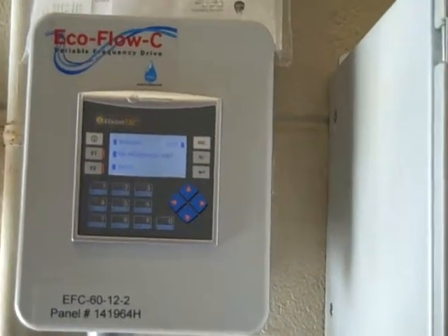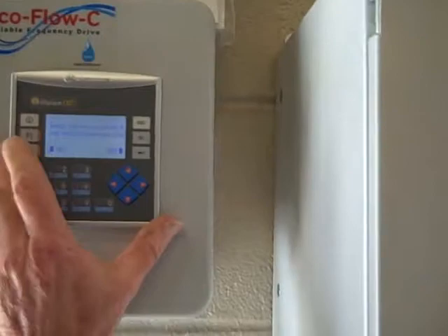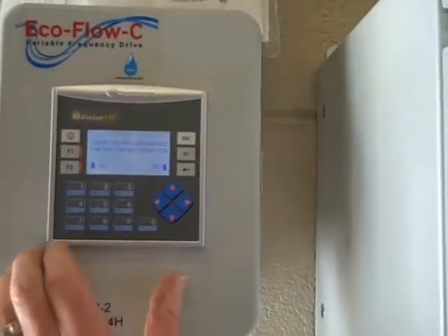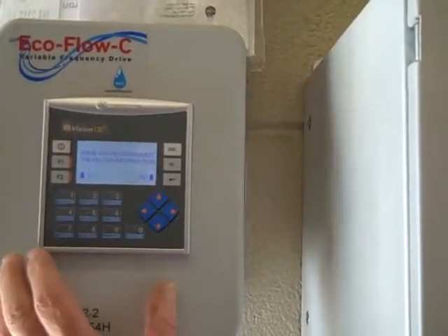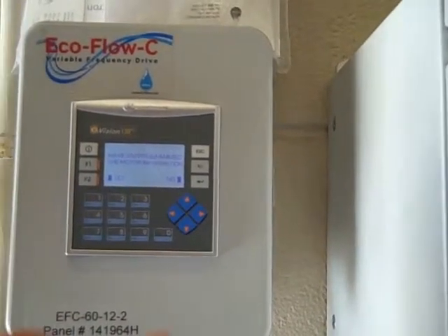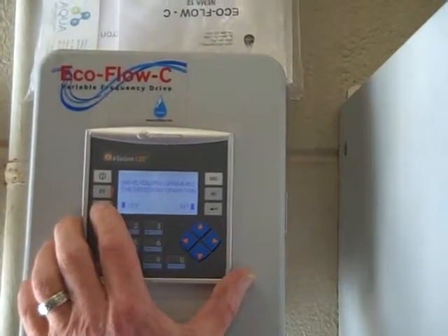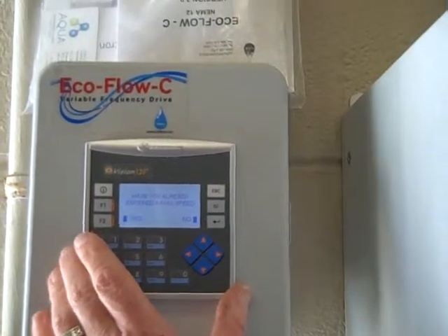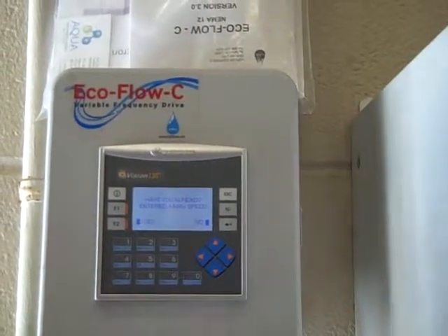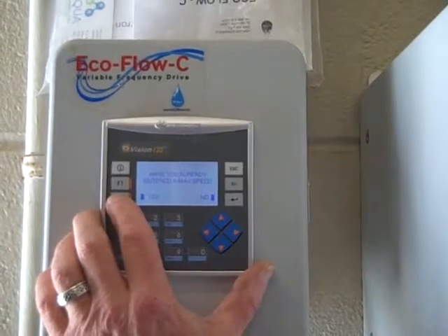Okay. Now, if we wanted to completely reprogram the unit, let's say you change pumps, and instead of the 1750 RPM, you got a 3400 RPM, you have to reprogram the unit. We don't want to go through all this, but we've already programmed the motor information. If we say no, it'll walk you through. What's the horsepower? What's the voltage? It'll walk you all through that. So we're going to say yes, we've already programmed the motor. We've already entered a max speed. If we say no, you enter a max speed. 94% is what we put up there. So we're going to say yes.